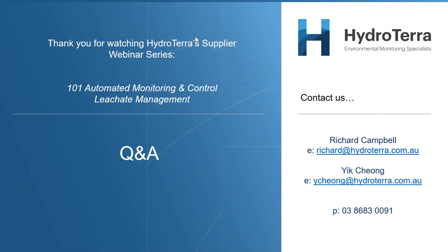Nilimbik has installed a telemetry system recently. We have two leachate ponds. Therefore, the bottom pond, where the leachate from the landfill flows, needs to be pumped to the upper evaporation pond. Question: is the telemetry system able to set up conditions for the two ponds before the pump can be activated to prevent overflow? Yes, so that was one of the examples we gave earlier, that can absolutely be done. As long as you've got good cell network on site, then you can use the logger boxes that are attached to the level sensors to talk to each other to switch power to a pump across two different sites. Yes.